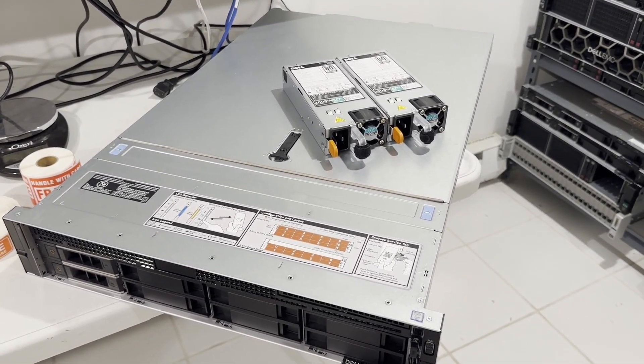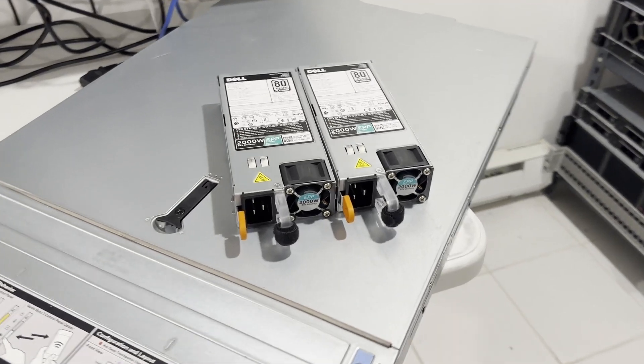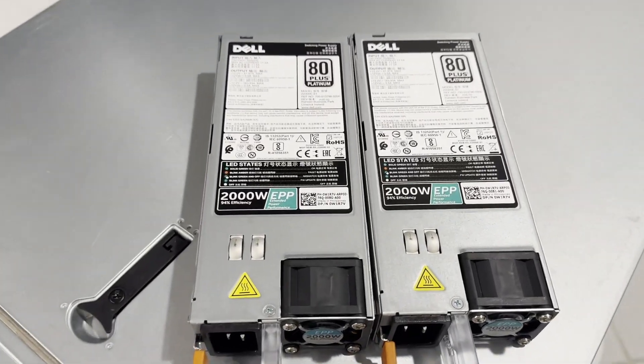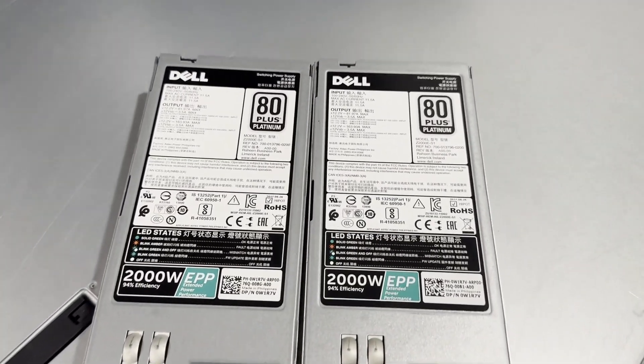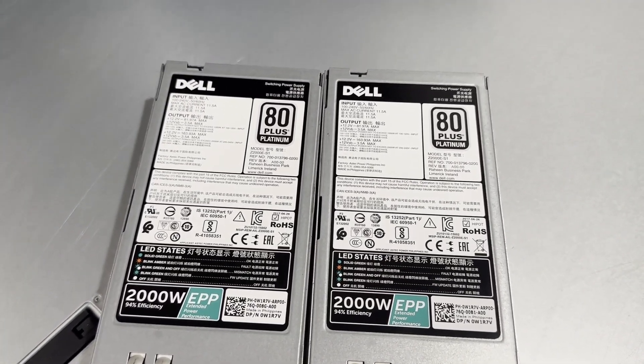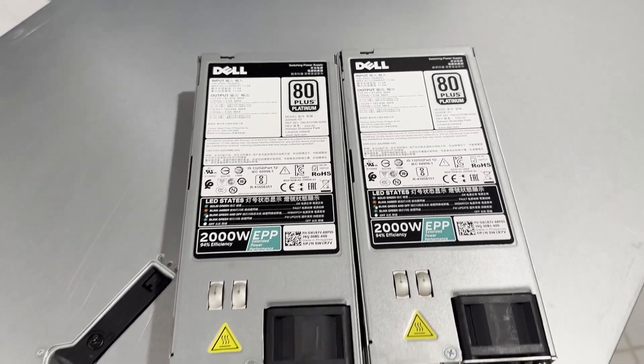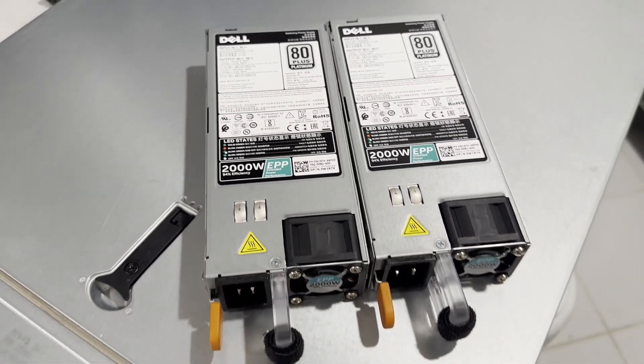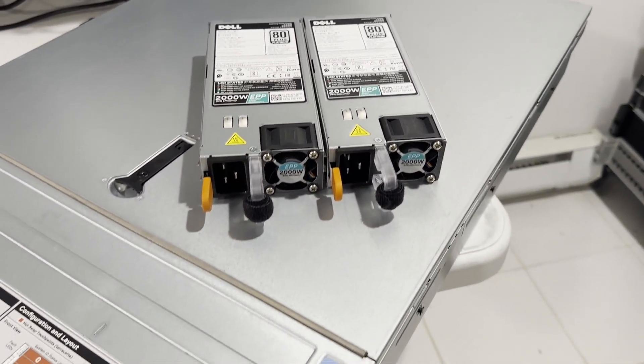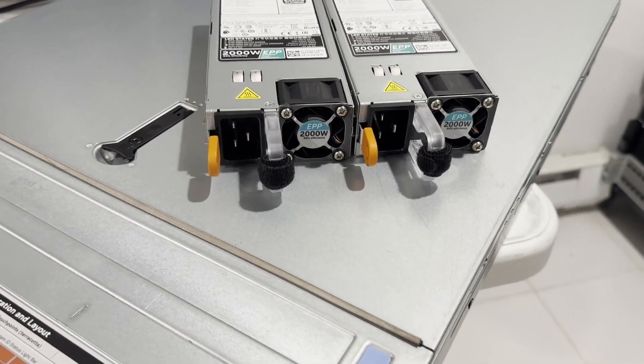We've acquired power supplies with a higher wattage rating. Each of these power supplies is rated at 2,000 watts, but they only deliver 1,000 watts when operating at 110 volts. It's important to note that these power supplies require a different type of plug, so you'll need to use different power cables.